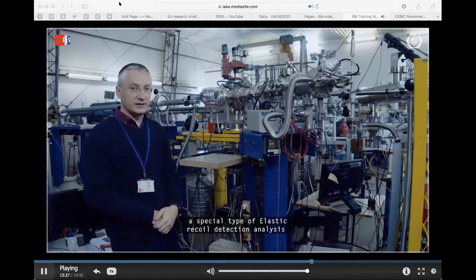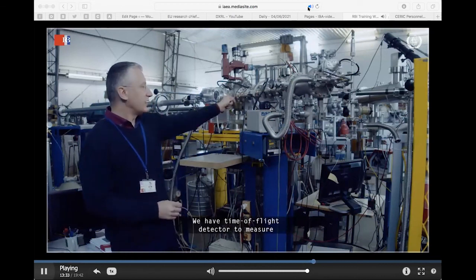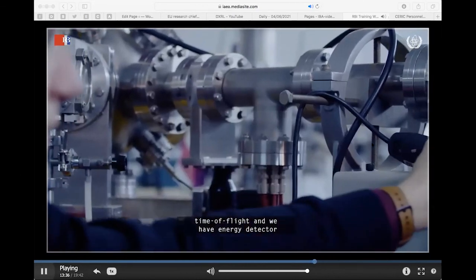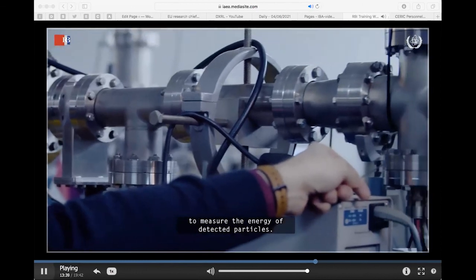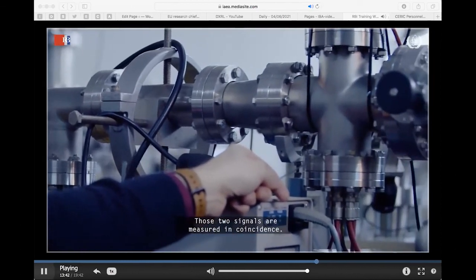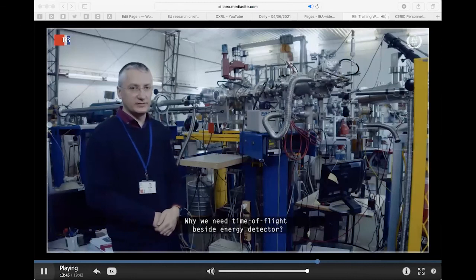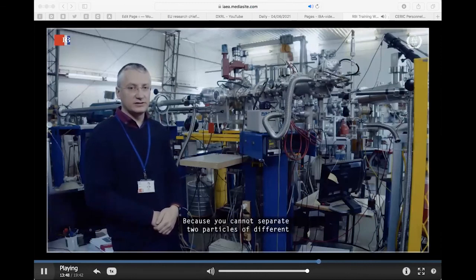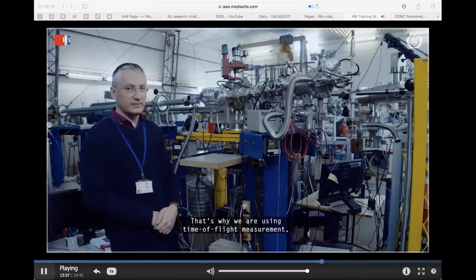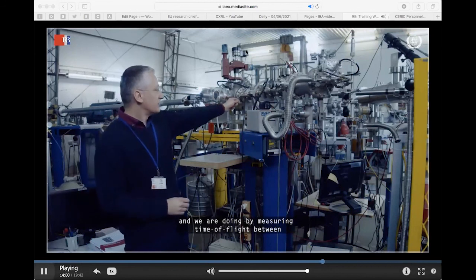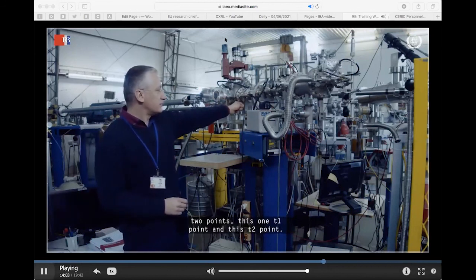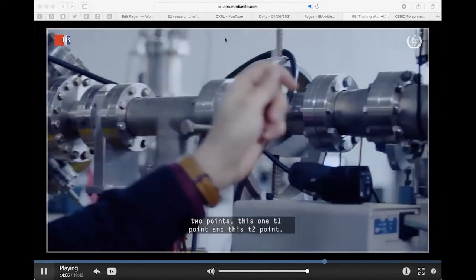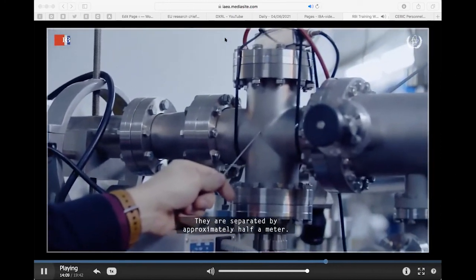This is a special type of elastic recoil detection analysis system because it consists of two types of detectors. We have time of flight detector to measure time of flight, and we have energy detector to measure the energy of detected particles. Those two signals are measured in coincidence. Why do we need time of flight beside the energy detector? Because you cannot separate two particles of different masses with the same energy using only an energy detector. That's why we are using time of flight measurement, and we are doing it by measuring time of flight between two points, this one T1 point and this T2 point. They are separated approximately by half a meter.